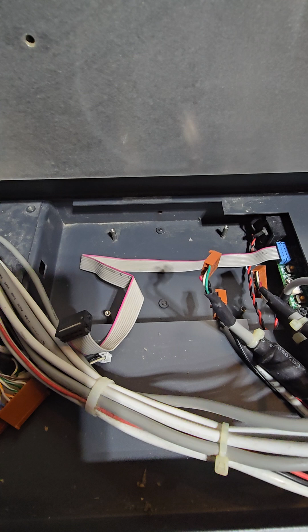Be aware, a new CPU board that you put in the system is not going to be flashed or programmed for your system exactly. It could be flashed from the factory as a different model, like a VLS 360, could be a VLS 460, 475, whatever. There are hotkeys to change that very quickly on your computer. And the same goes with any other settings that you have saved, meaning Z-axis calibration, rotary fixture calibration, flat table calibration, all very simple things to take care of once you install your new CPU board. And that's it. I hope this helps.